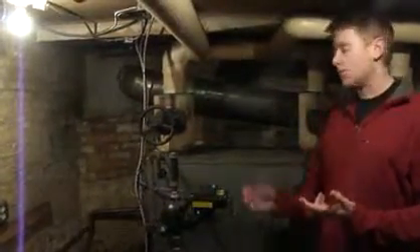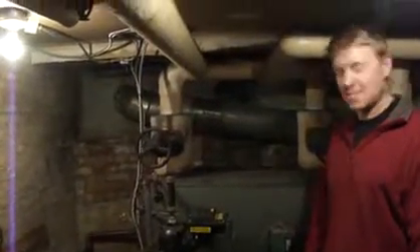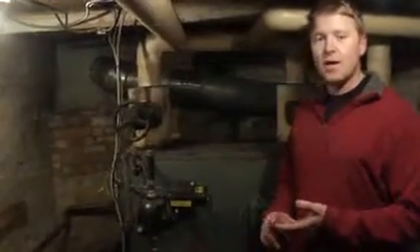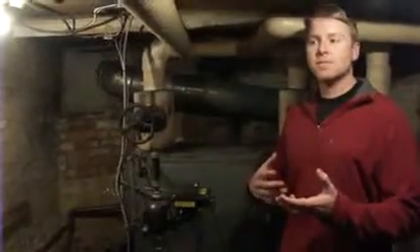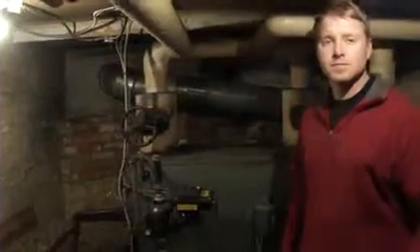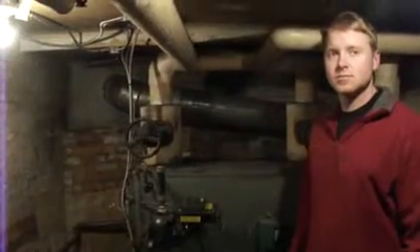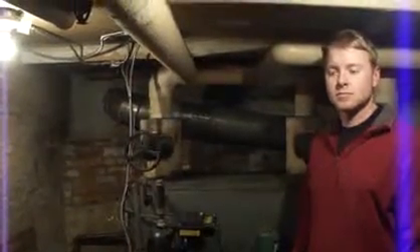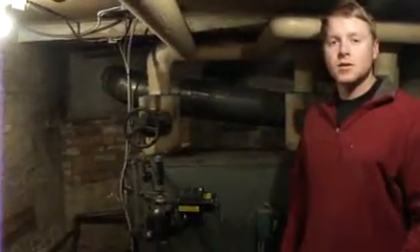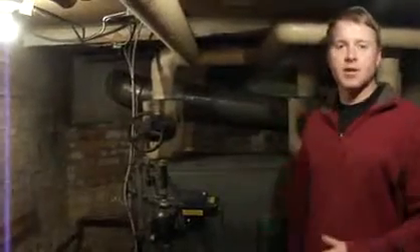It's going to tell them the stack temperature of what they're losing, and help the contractor adjust the efficiency up or down. So if a customer in their house has a boiler working in the mid-70s, they know that potentially 30% of the fuel usage is being burned up going up the chimney, and not being used for heating their home. It's just going through the boiler into the chimney and outside — and they're losing that.